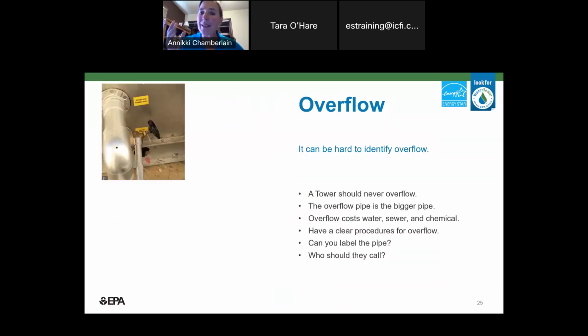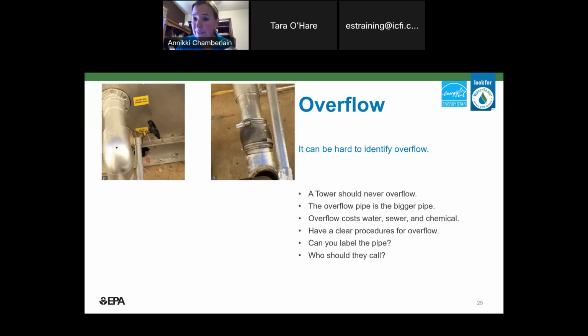Also, with overflow, a lot of these systems are not set up to be seen very easily. It was a video, so I tried to do some screenshots, but a tower should never overflow. We can typically identify the overflow because it's the larger pipe, almost always. I would bet $100 that it's always going to be the larger pipe. Sometimes at big facilities they might be the same size, but it basically has to keep up with a wide open makeup valve that gets stuck on.